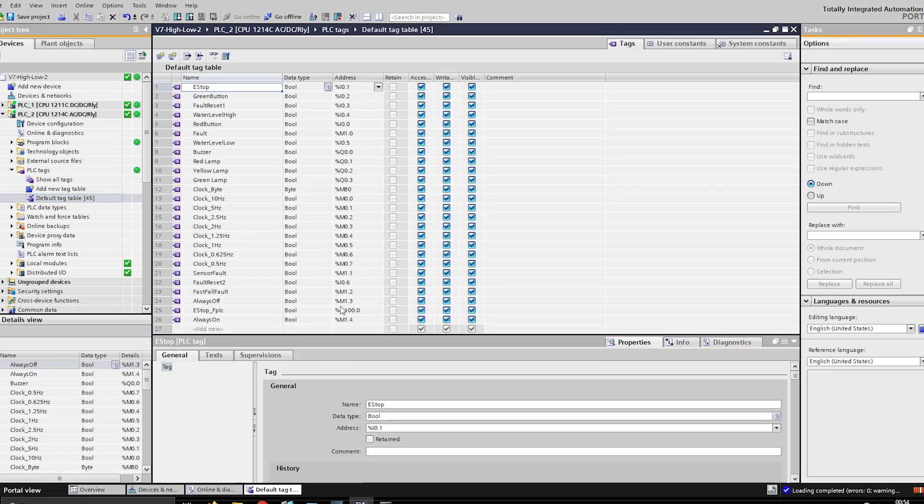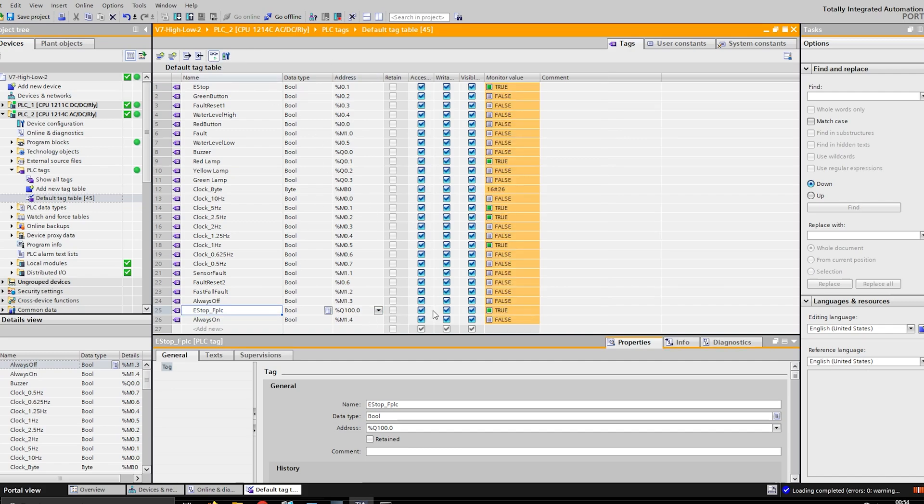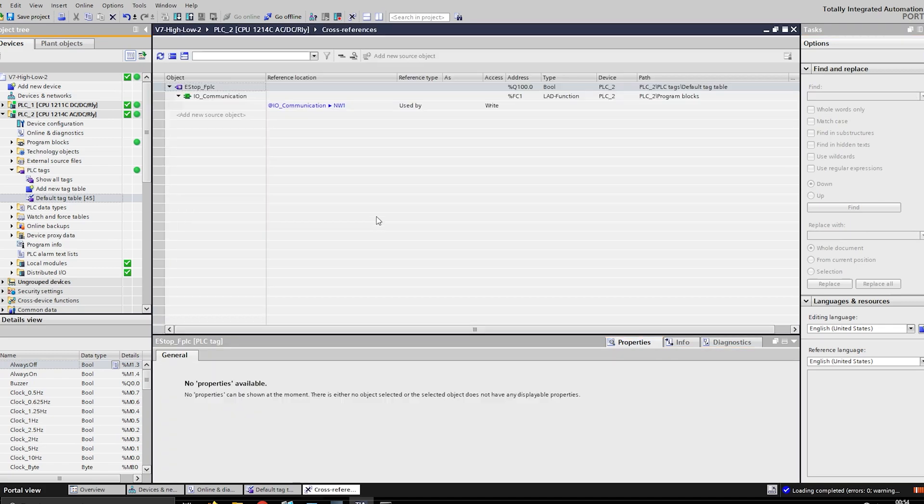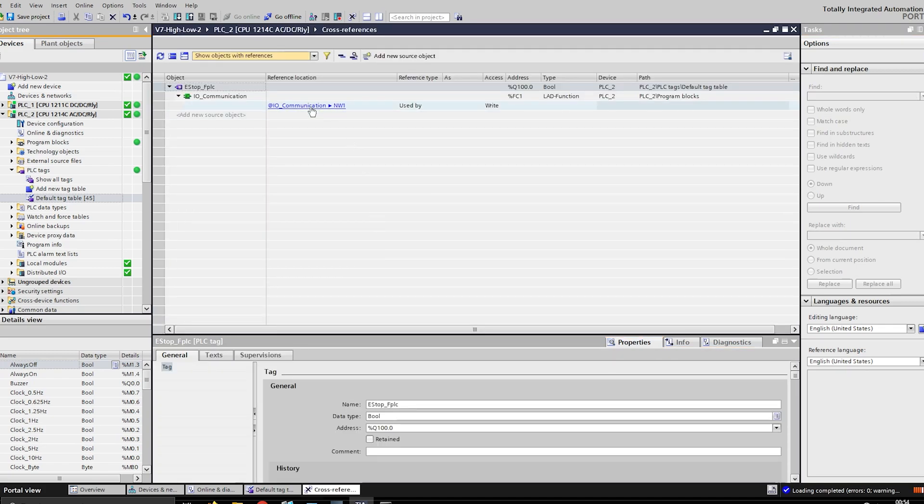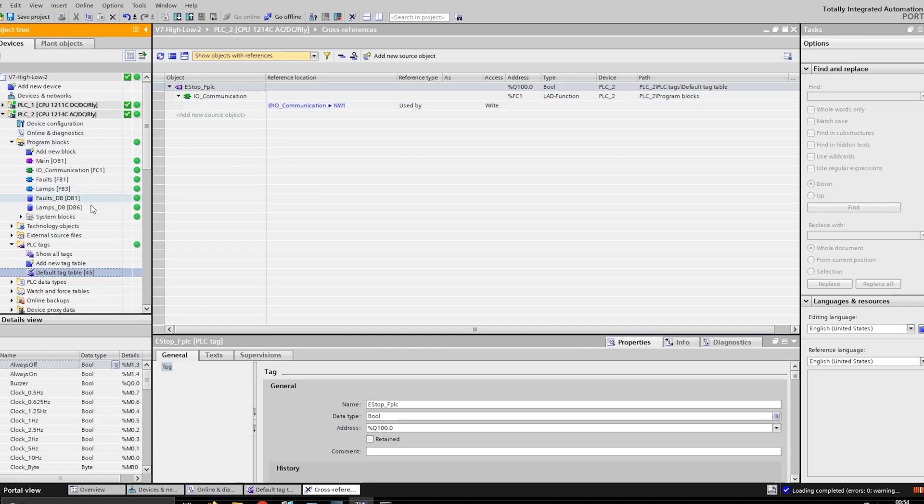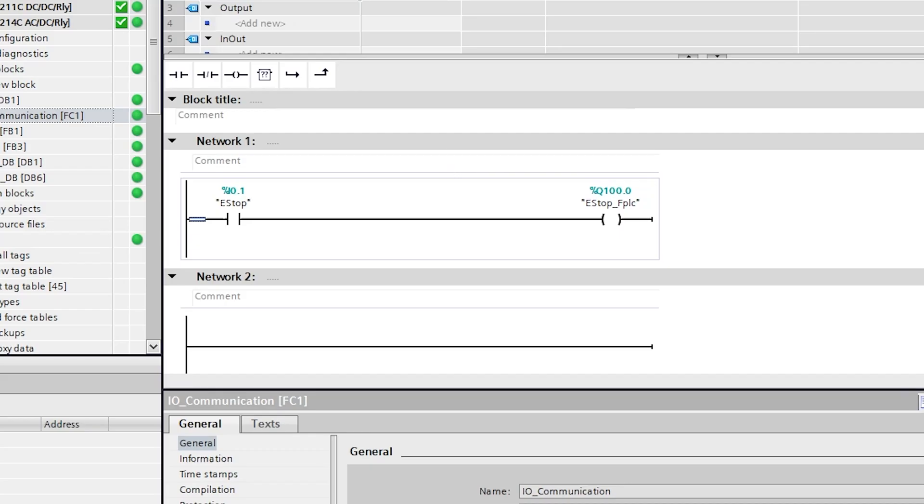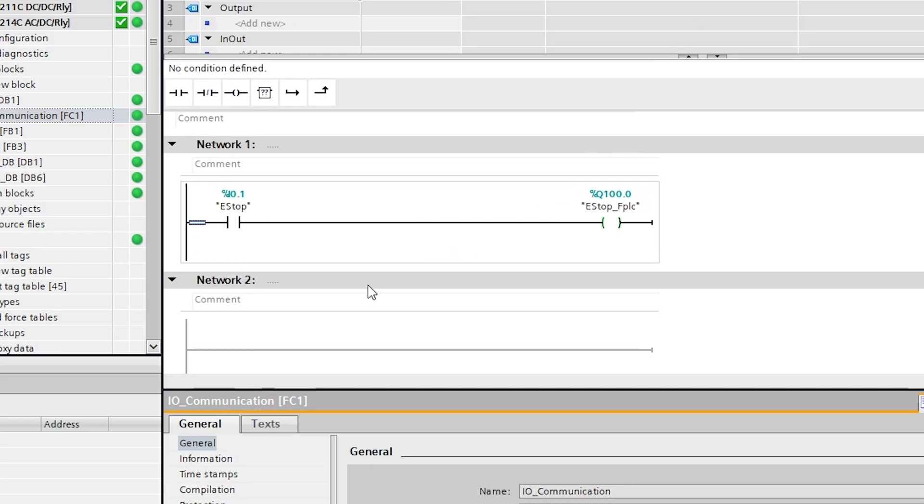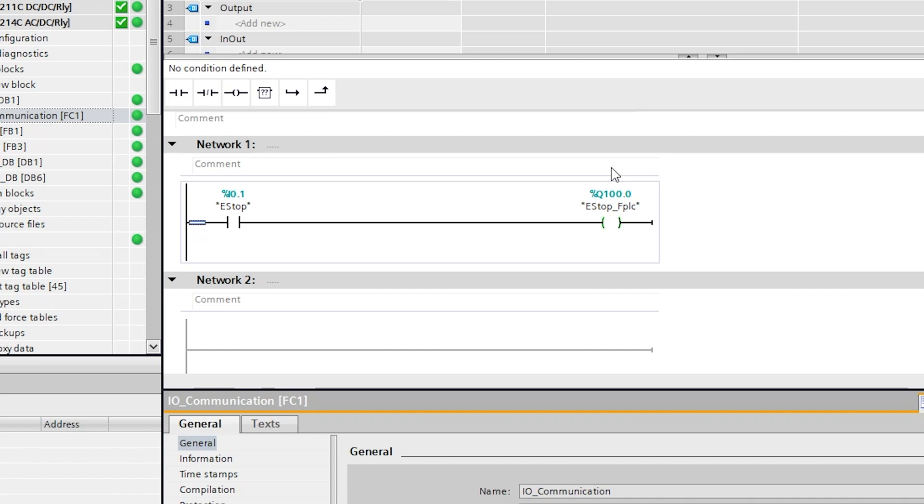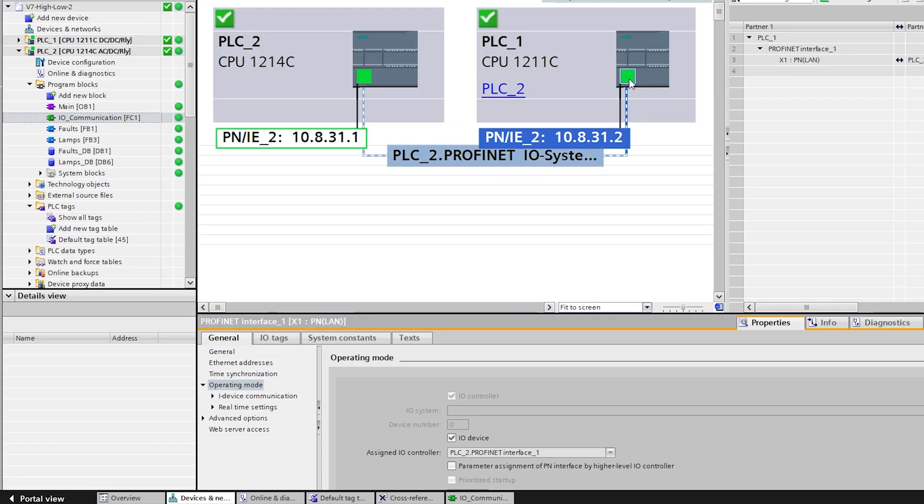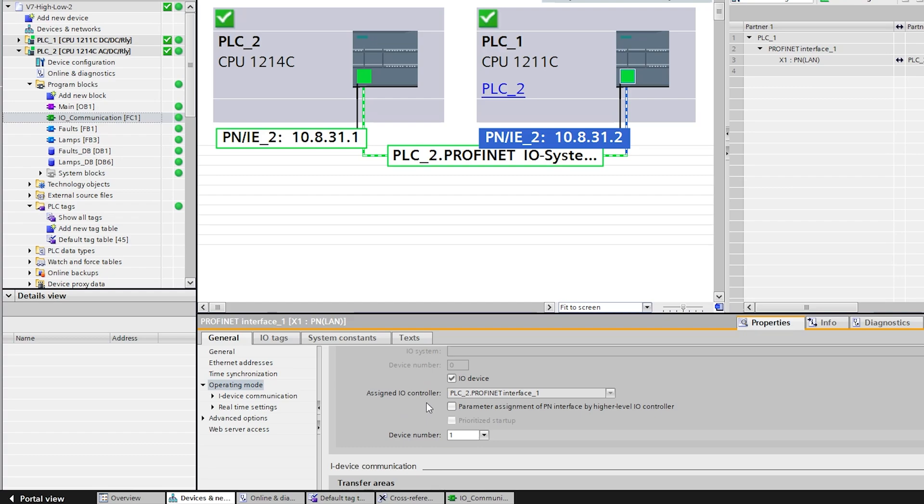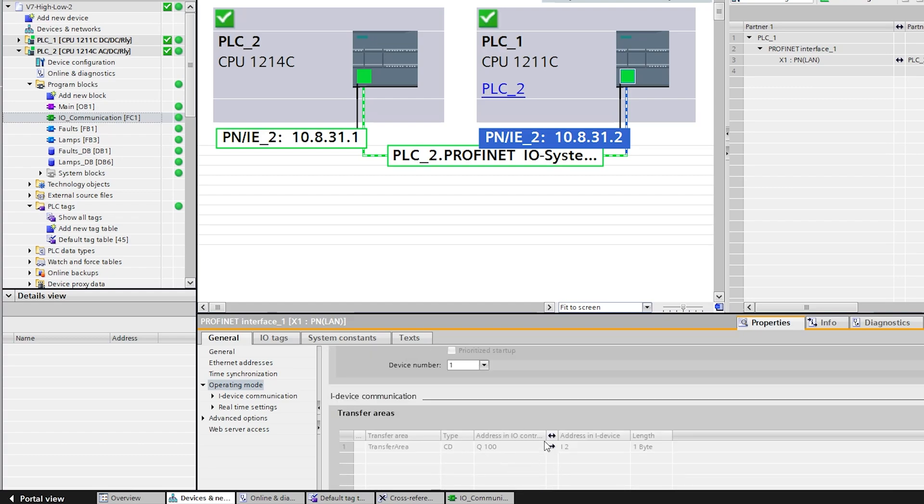If I go on to this PLC, PLC2, and I go to my tags, we're looking for Q100. There you go, Q100 is there. That's currently set to true. If I cross-reference it you can see where it's used. What I did was I made a block called IO Communication. Here what I've done is I've sent my normal E-stop input, which is just input 0.1, and I've sent that input to an output Q100. Obviously my 1214 doesn't have 100 outputs, but you can still reference and use outputs you don't physically have. I've sent that to Q100 and I've specified that here in my ethernet port operating mode - send that address Q100 and send it to input 2 on this PLC.